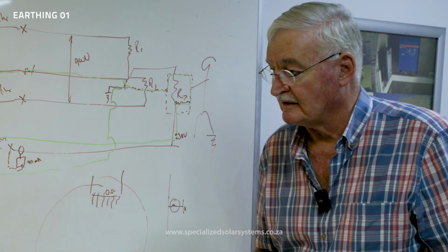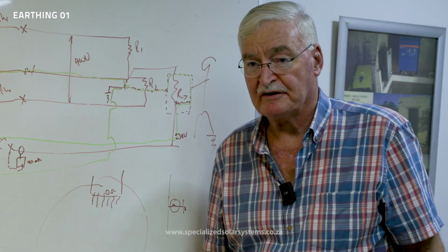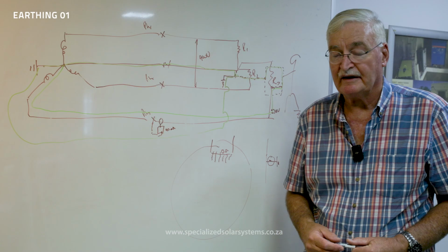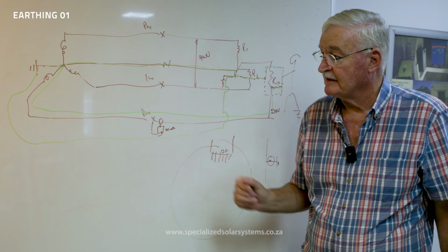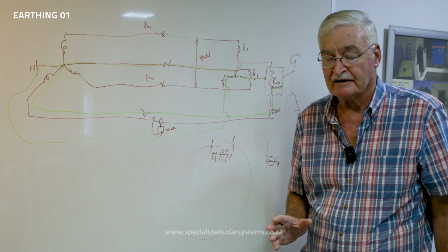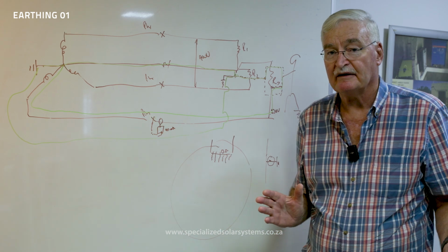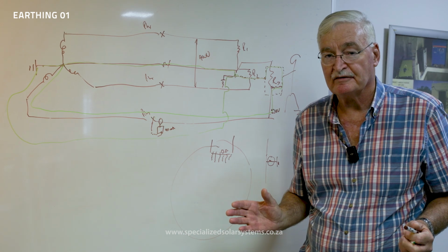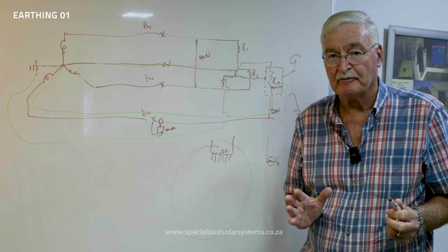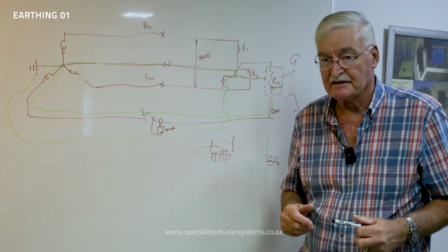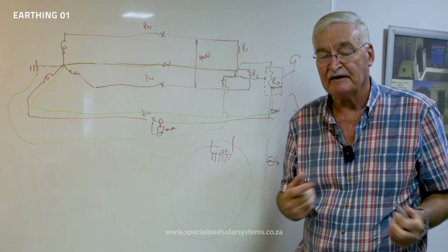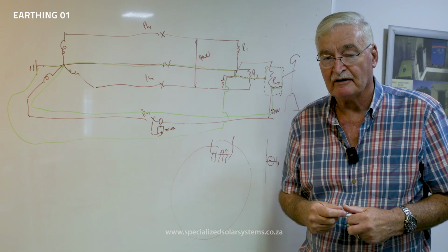reasons. Now, when you look at your specific type of equipment, one has to be very careful in applying the earth philosophy, because most inverters don't want the primary and the secondary earth connected to one another, because of the electronics and the way it operates. So in the case of, like, the Victron inverter, they have a switch inside that will automatically create an earth path.